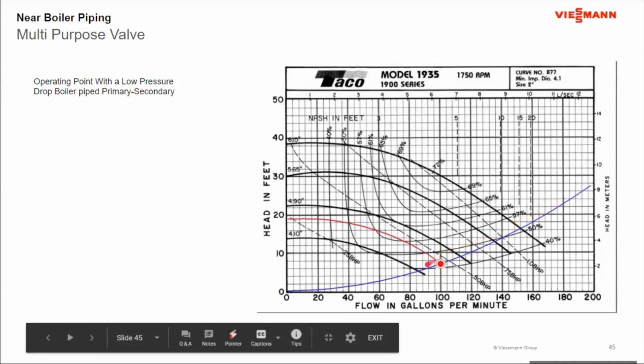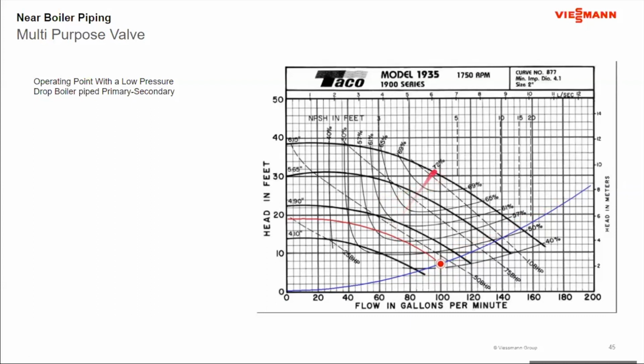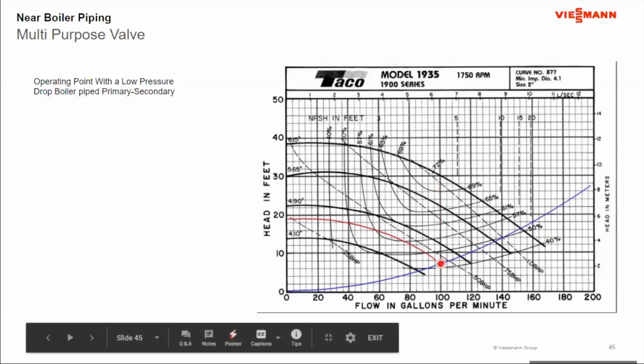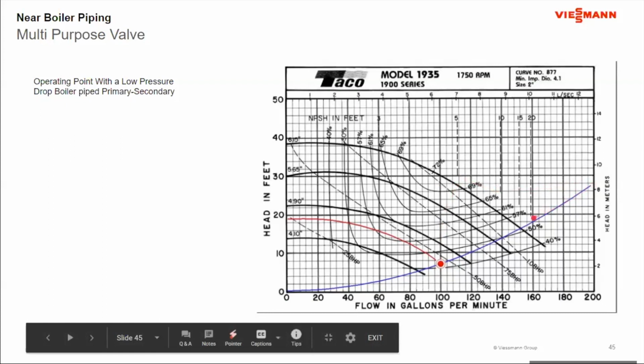The blue is my system curve. From an aspect of pump operation, the closer to the center you are here, the better the pump operation is going to be, the higher the efficiency, and the pump and the motor will last longer. So if I don't put a balancing valve in and I sit here, I am compromising the longevity and the performance of my pump. Now, if I do a VFD, the VFD doesn't change the system curve. The VFD moves the pump curve up and down, expands and contracts it. So I will just continue to move along this line no matter what you do with that VFD. The balancing valve will bring me up to here.